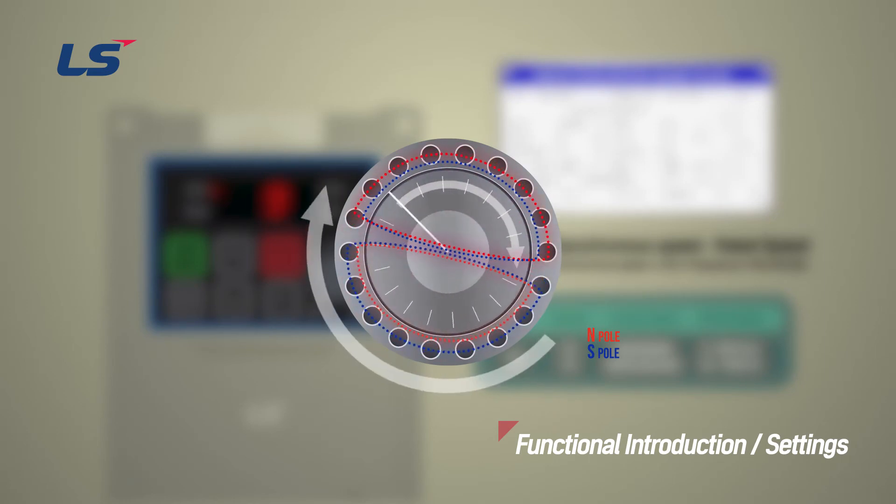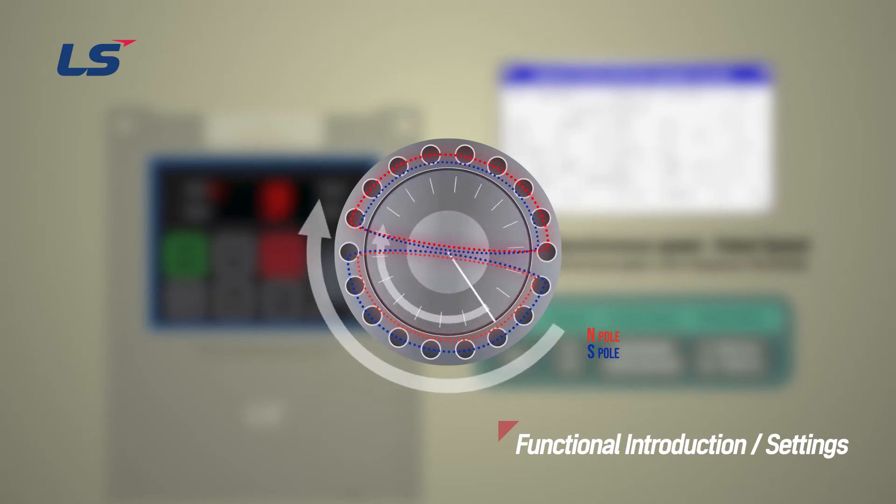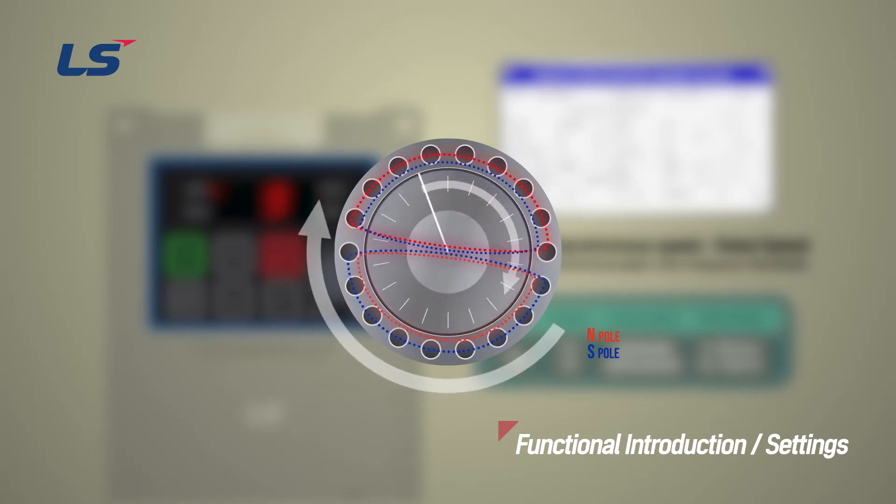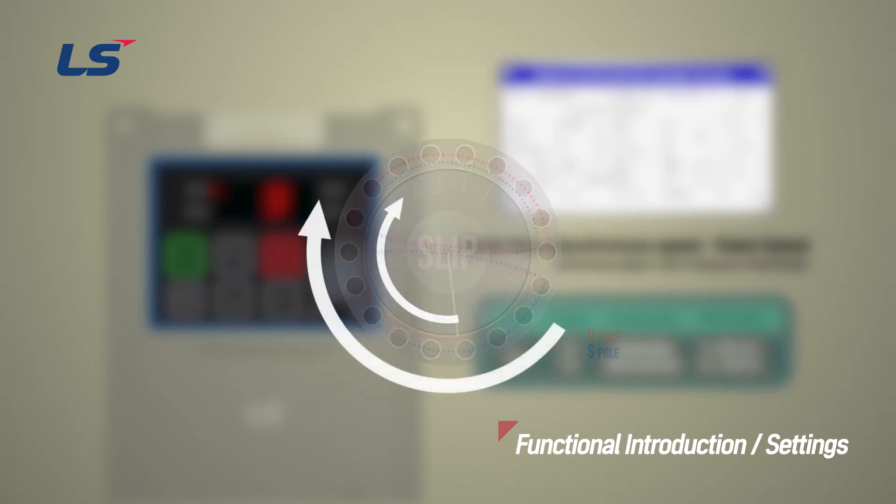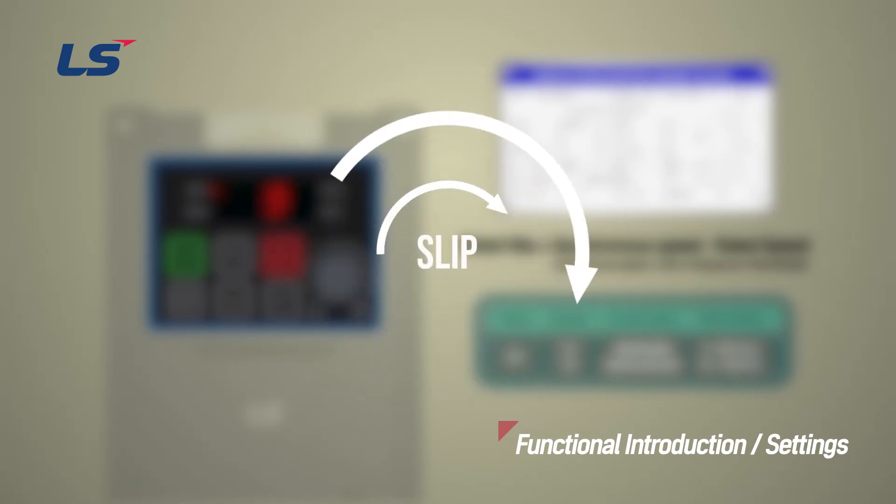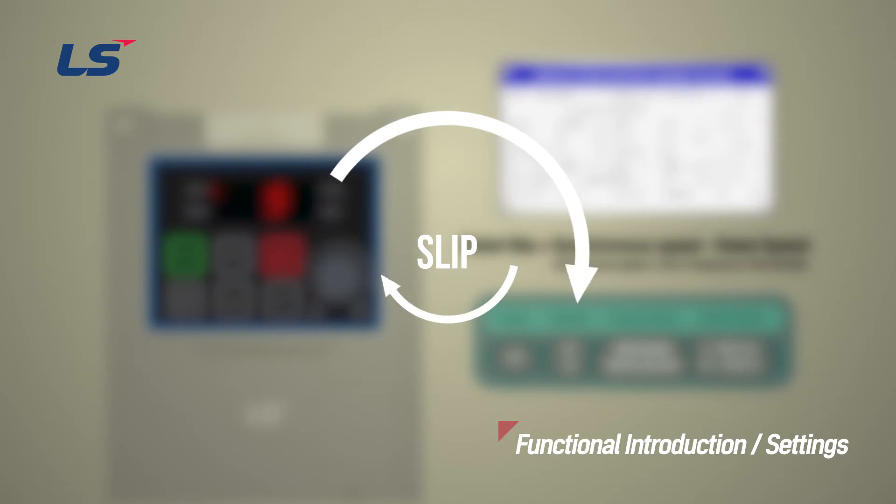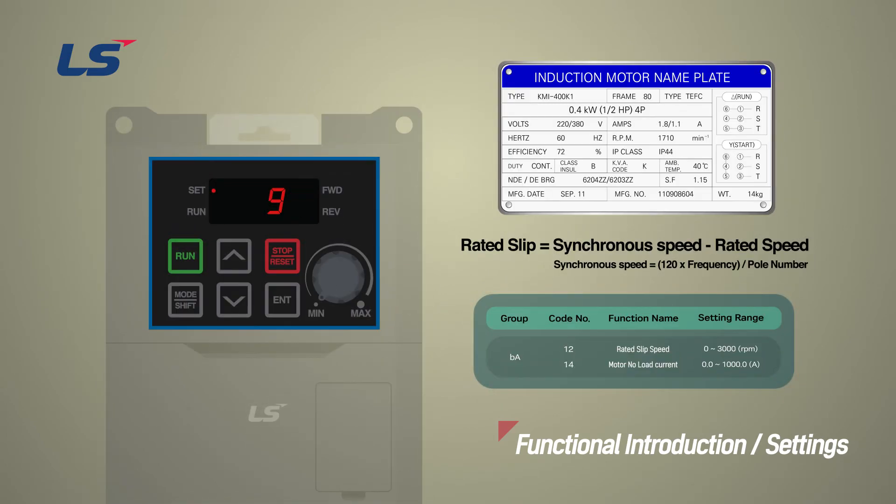At this time, the rotor rotates at a lower speed than the rotating magnetic field due to the resistance of the load, and the difference in speed is called slip. The slip is not indicated on the nameplate of the motor, so the difference must be calculated and entered.